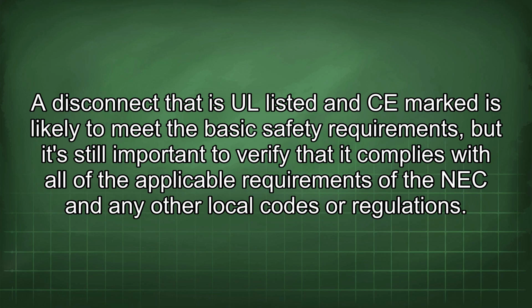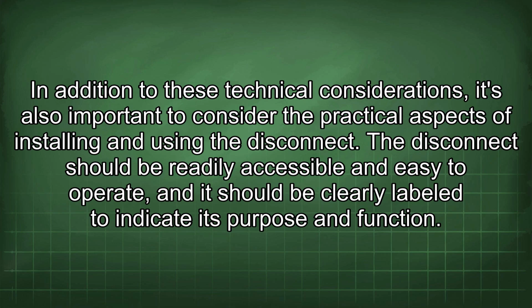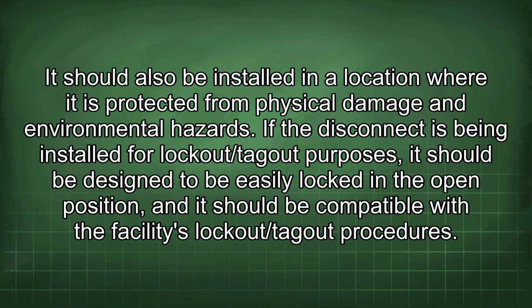In addition to these technical considerations, it's also important to consider the practical aspects of installing and using the disconnect. The disconnect should be readily accessible and easy to operate, and it should be clearly labeled to indicate its purpose and function. It should also be installed in a location where it is protected from physical damage and environmental hazards. If the disconnect is being installed for lockout/tagout purposes, it should be designed to be easily locked in the open position, and it should be compatible with the facility's lockout/tagout procedures.